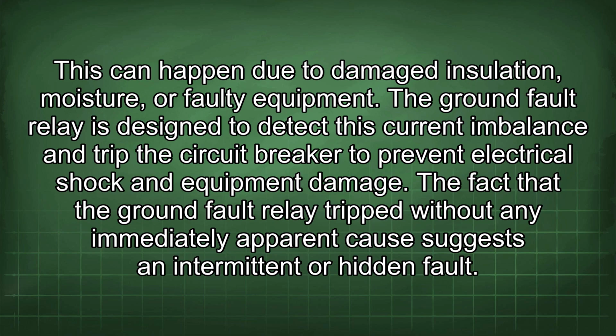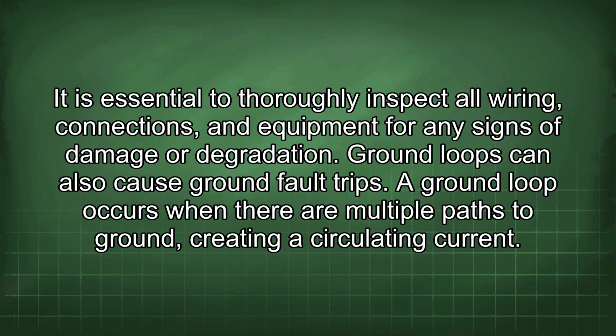The ground fault relay is designed to detect this current imbalance and trip the circuit breaker to prevent electrical shock and equipment damage. The fact that the ground fault relay tripped without any immediately apparent cause suggests an intermittent or hidden fault. It is essential to thoroughly inspect all wiring, connections, and equipment for any signs of damage or degradation. Ground loops can also cause ground fault trips.